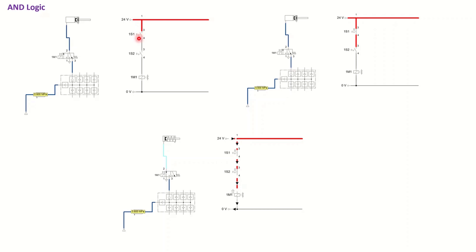If I turn on 1S1 and turn on 1S2, the system can operate — basically the current can pass from 1S1 and 1S2. Therefore 1M1 is going to be energized and the system starts operating, which means 1M1 is energized and the solenoid connected to 1M1 is going to shift the directional control valve. Once it is shifted we would have the next action inside the pneumatic system.